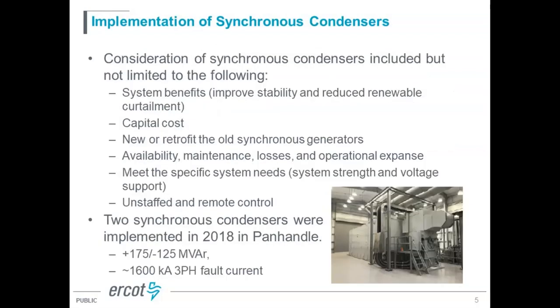Once we determined the need for condensers, in terms of implementation and the selection of the synchronous condensers, here is just a very high-level overview for the group. There are many items not on the list that were considered when the condensers were selected and implemented. Obviously, as always, the first consideration for the device, here the condensers, is what kind of system benefit they can provide. In this case, they definitely improve our stability in the Panhandle.